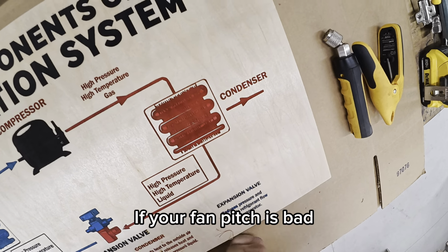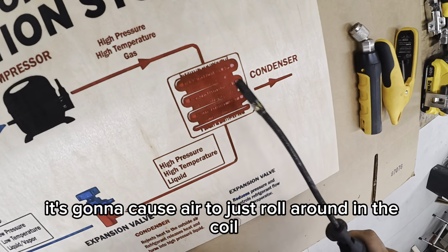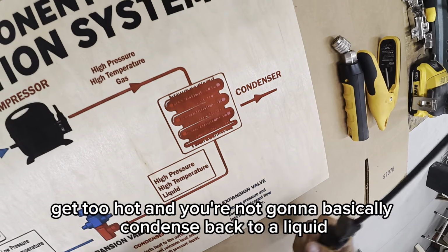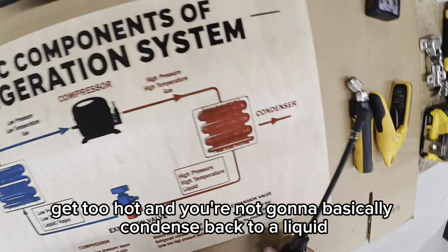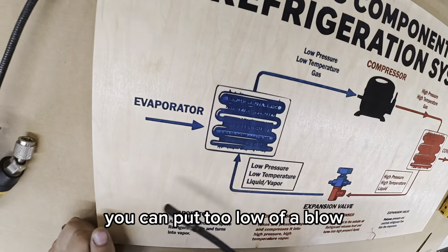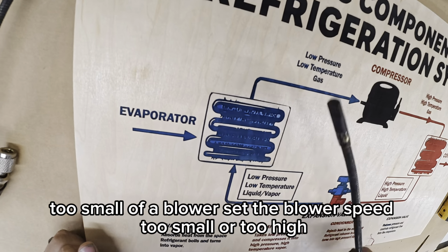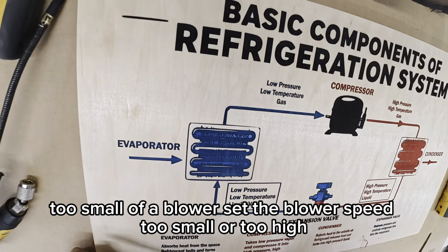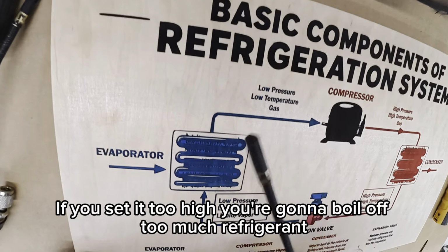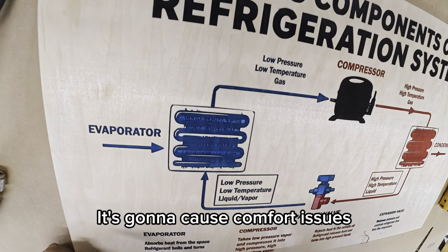If your fan pitch is bad, it's going to cause air to just roll around in the coil, get too hot, and you're not going to basically condense back to a liquid. Same thing with the indoor. You can put too small of a blower, or set the blower speed too small or too high. If you set it too high, you're going to boil off too much refrigerant, right? It's going to cause comfort issues.